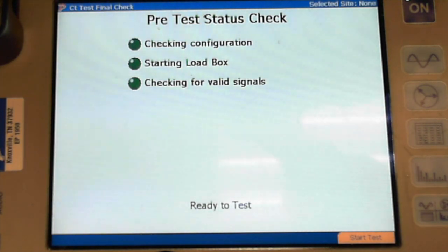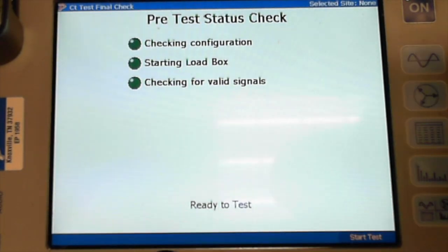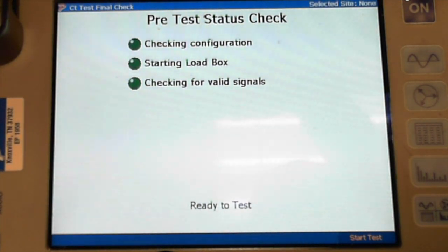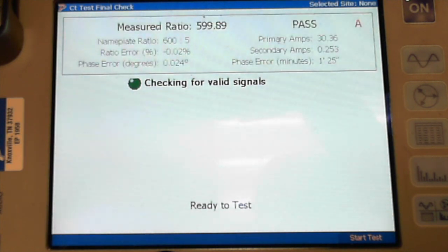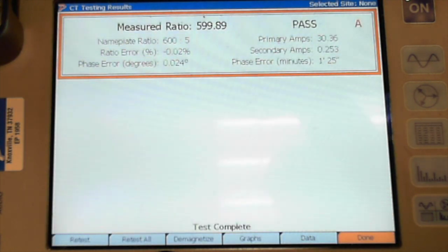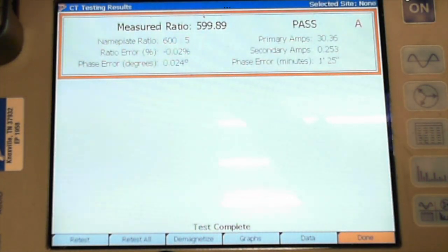All right, so the load box is stabilized, and I'm going to go ahead and press Start Test to test the CT. So that test came out pretty darn perfect. So again, this is a 0.15 S CT. That means at 100% rated load, within the range of the CT, you're guaranteed 0.15%. I am measuring 0.02%. Fantastic. I'm not sure you can ask for anything more.